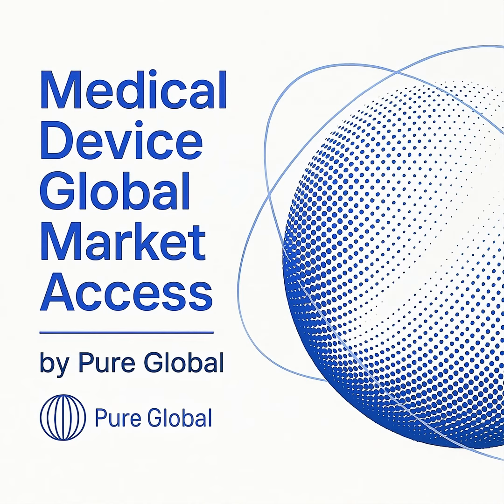Beyond these foundational documents, your device's specific characteristics will dictate further standard selection. Does your device need to be sterile? Look to standards like ISO 11135 for ethylene oxide sterilization or ISO 11607 for packaging. Is user interaction key to its safe operation? Then IEC 62366 on usability engineering is essential.